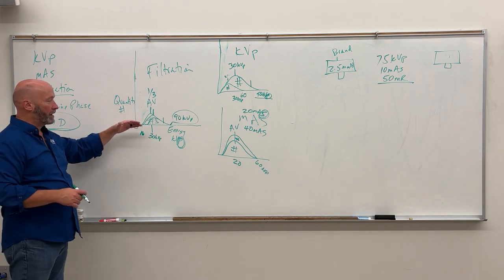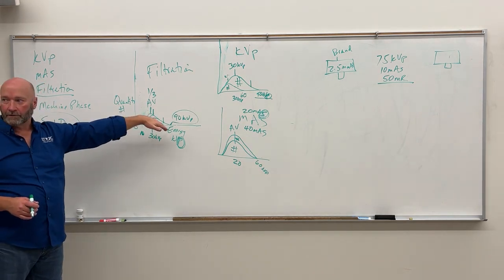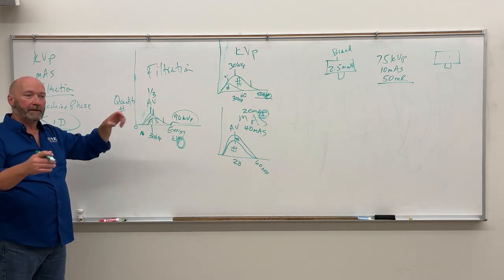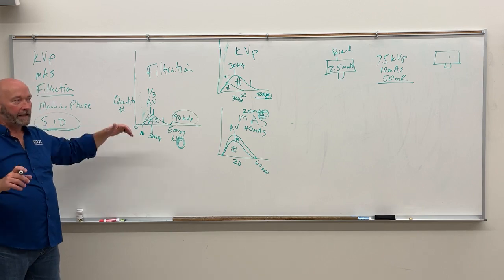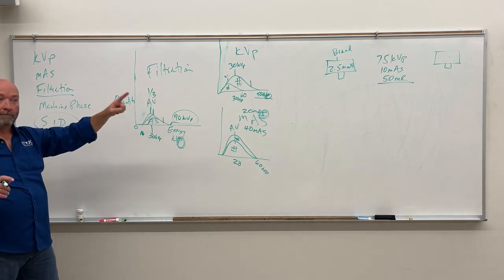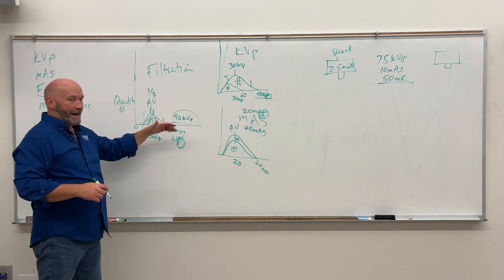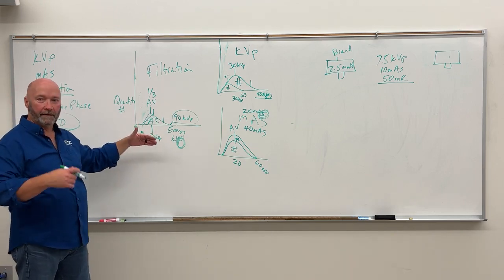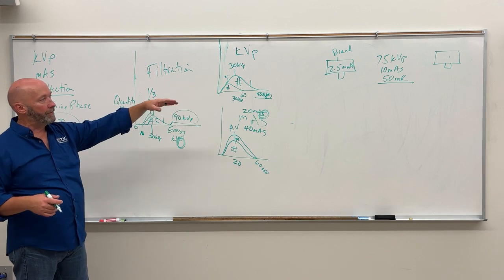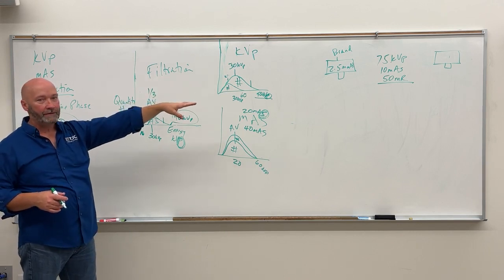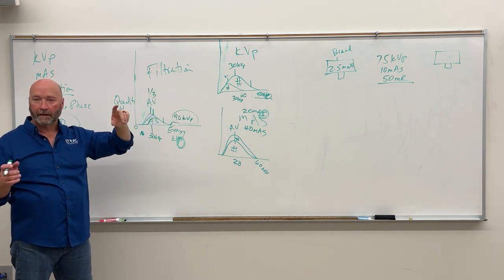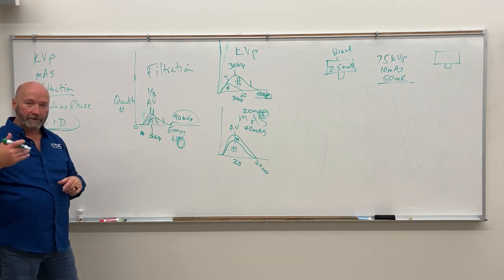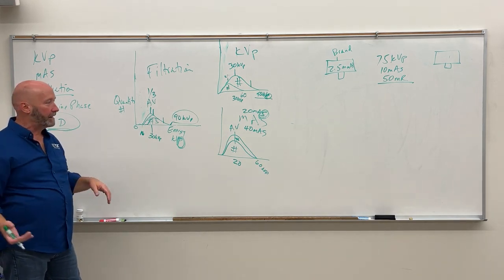Okay? So you're going to lose numbers every year that you use a single X-ray tube, and they're going to have to tweak it to get it back to the same radiation exposure. Let's say in year one, they come in and our radiation output is down about 5 below that. What are they going to have to do? They're going to have to up it until it's at 50 again.